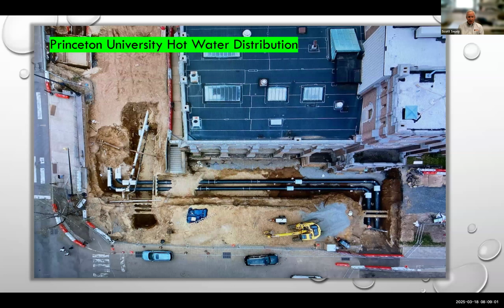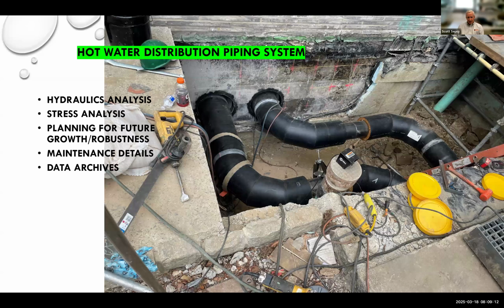And this is an overhead view of our new district hot water system being installed, one branch of 14-inch piping. A close-up of the building entrance for the hot water coming into one of the science buildings. On hot water distribution piping systems, you have to consider the hydraulics of the building. You have to do stress analysis, plan for future growth and robustness of the whole system, and you have to keep good track of what you've put in and how you're going to maintain it.